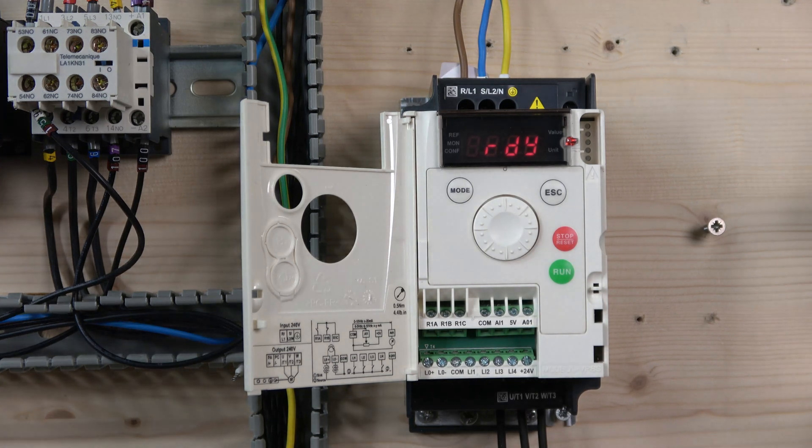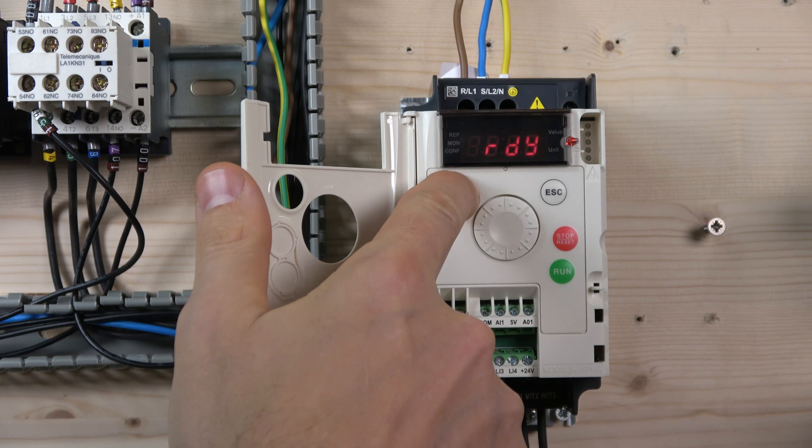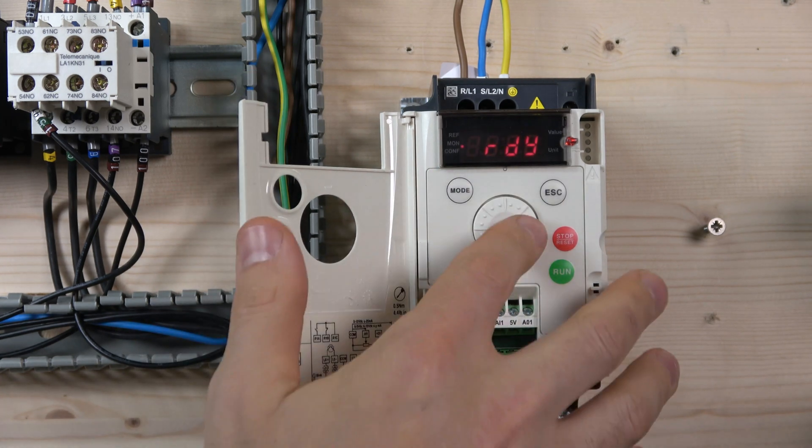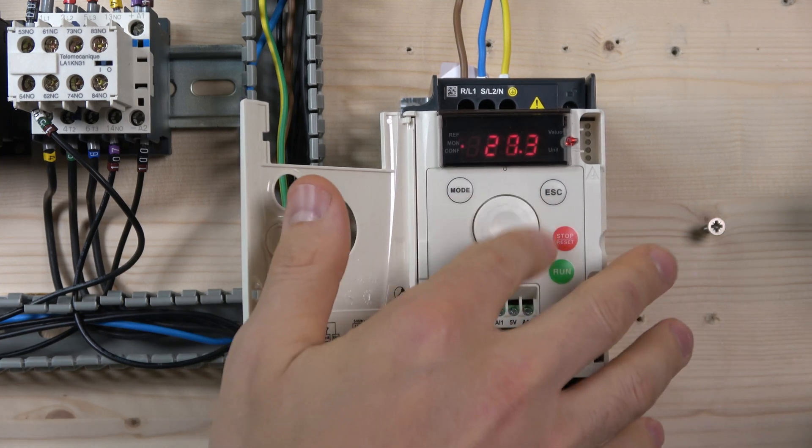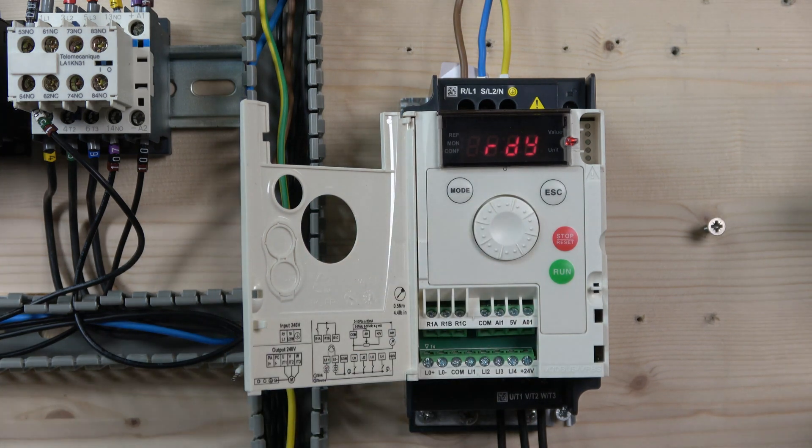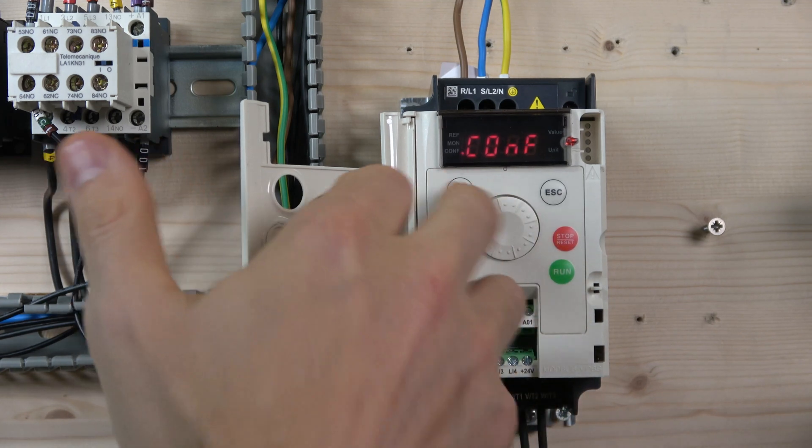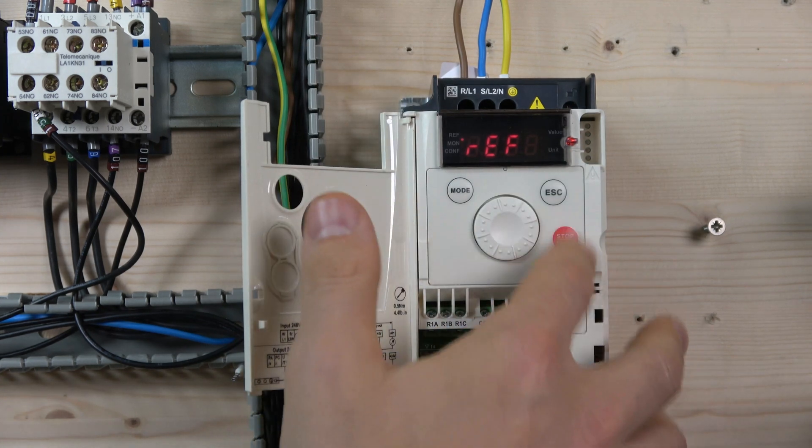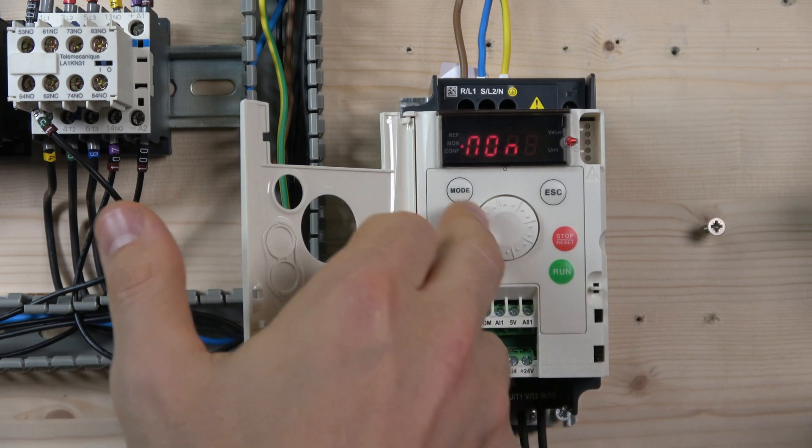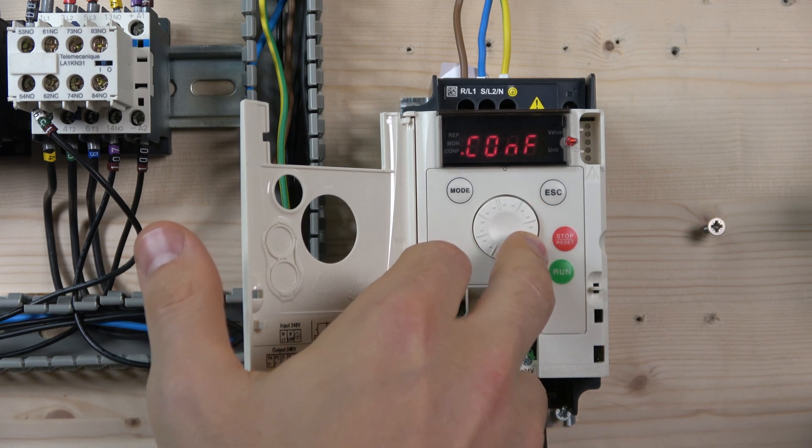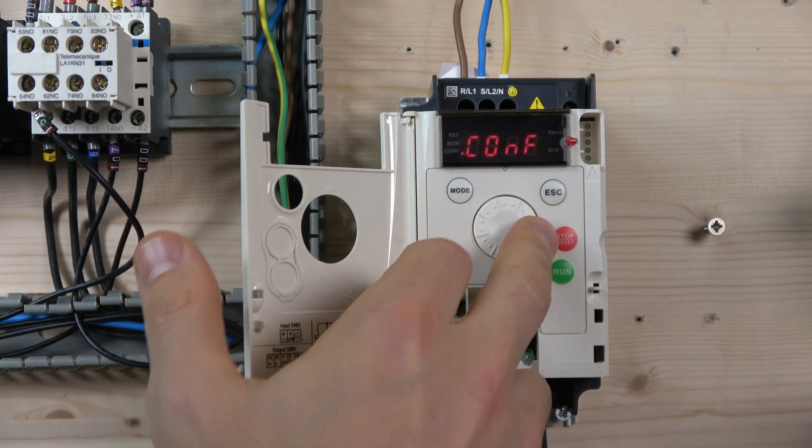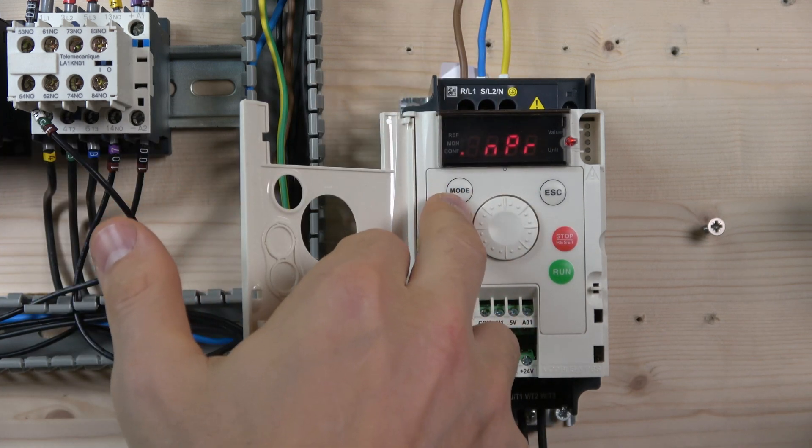Regarding the front keypad: the mode button, if you hold it down, goes to local mode. In local mode, you can control the frequency, start and stop, everything from the front keypad. Holding it back down switches modes, but you can't edit any parameters - you have to be in remote mode for that. We've got the escape button, start/stop, reset, and this dial is called the jog wheel. We'll be playing with all our parameters using this. Click the middle to go into a parameter and click through everything.